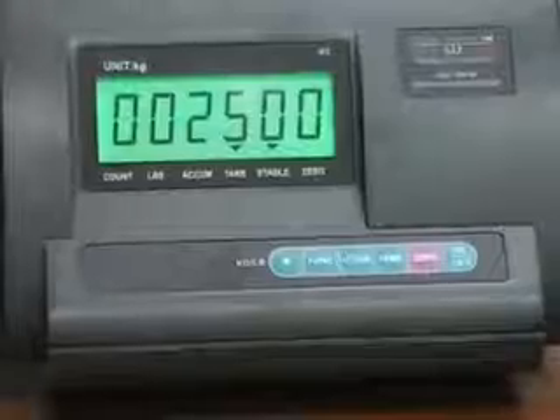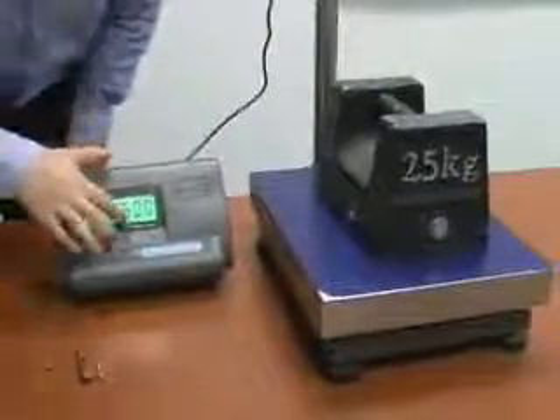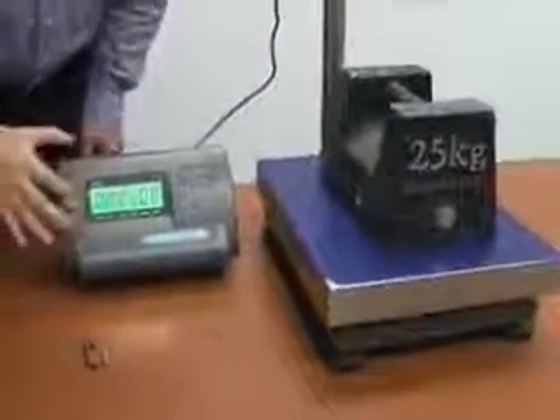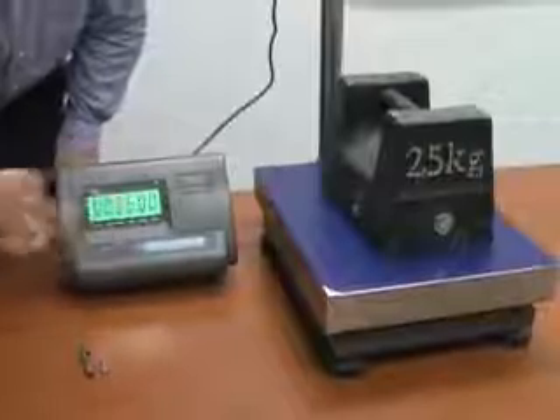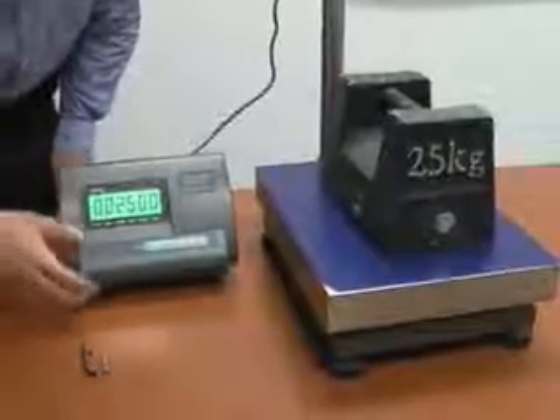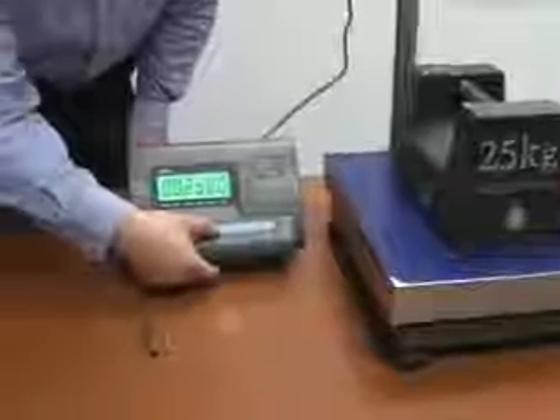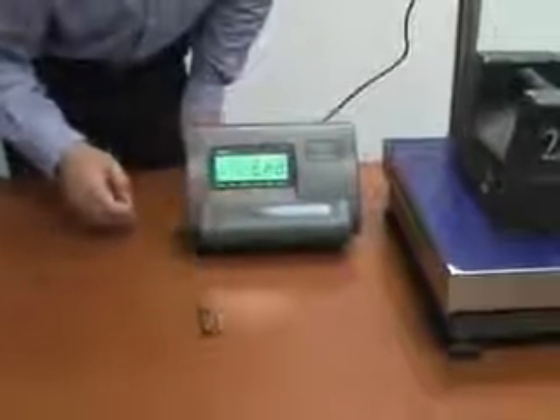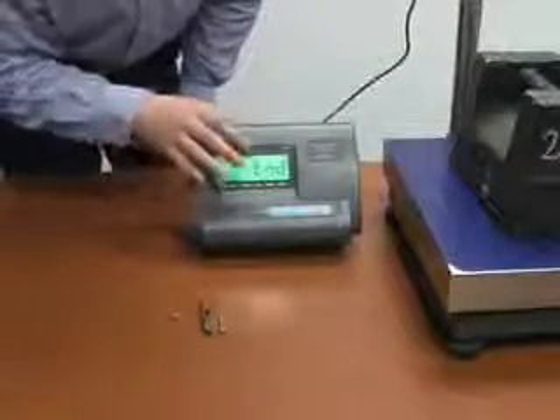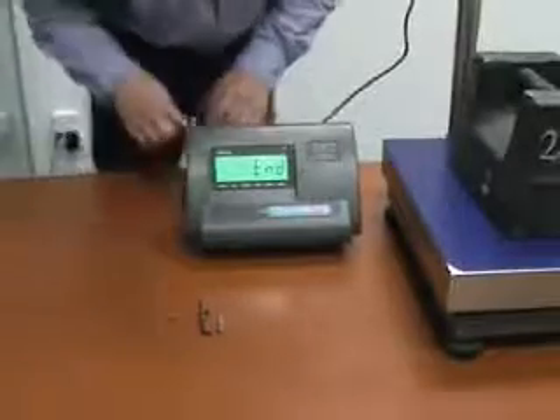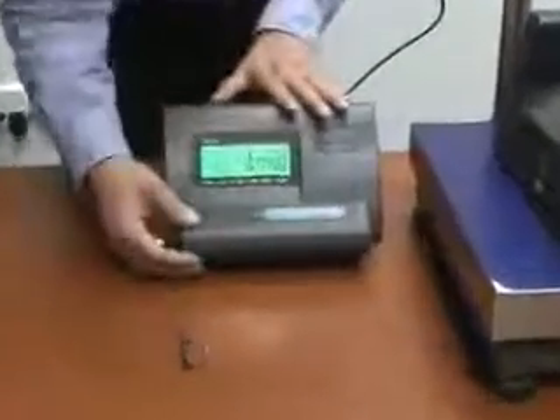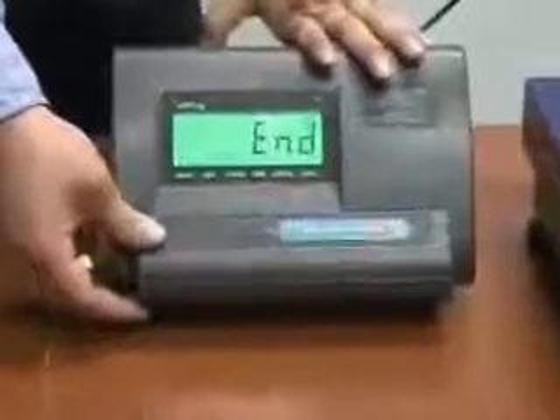Now we can put the calibration weight on the center of the platform and check the stable sign. If it's on, that's good. If there's no sign, there's some communication problem. When it's done, press the pound key. Then it gives you end. End means calibration is ready, but the indicator will not remember all the changes we gave it until you press the little button on the back, which is the confirmation key.